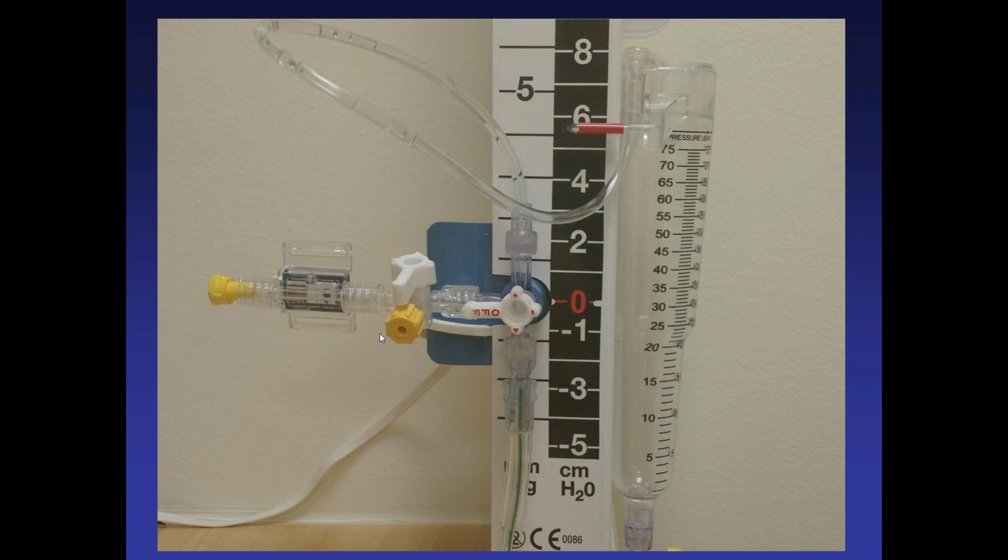I mean, the more dangerous is when it's only off by 10. It's not off by like 20 or 30, right? Because then you have a plausible number. So if you see this and you have some reason to really have an accurate ICP, take this thing off and zero it yourself.